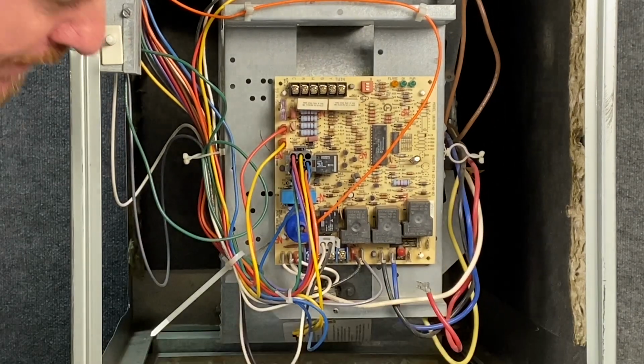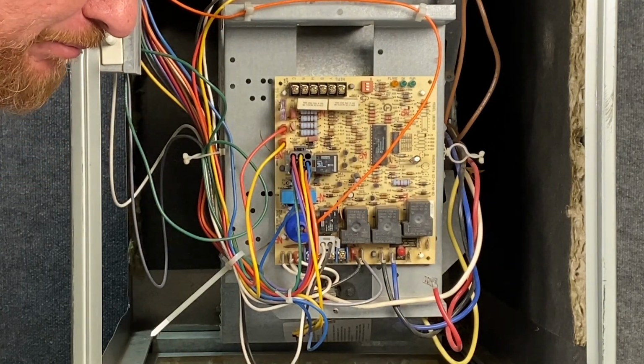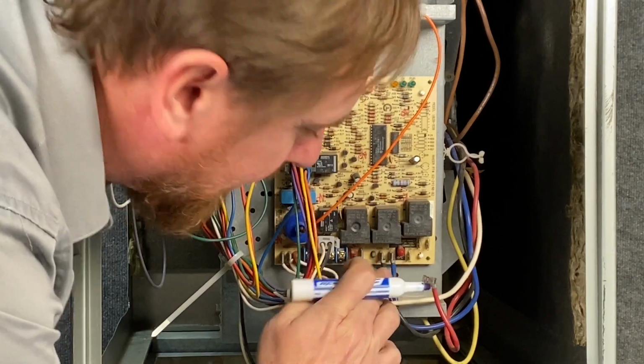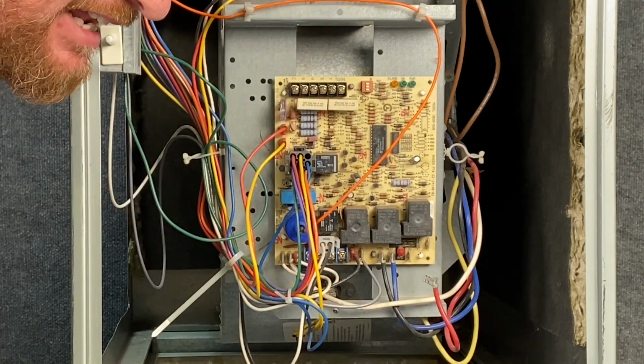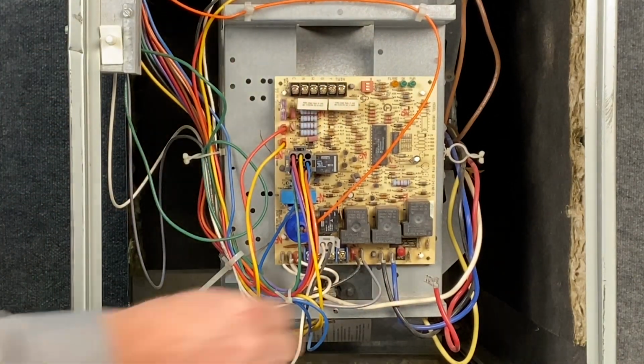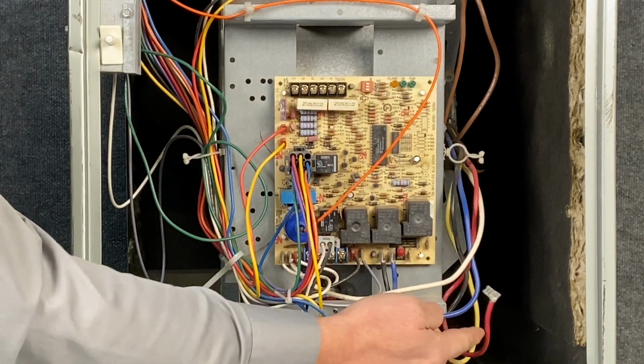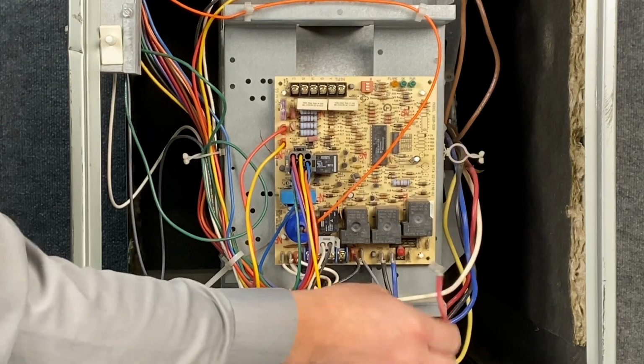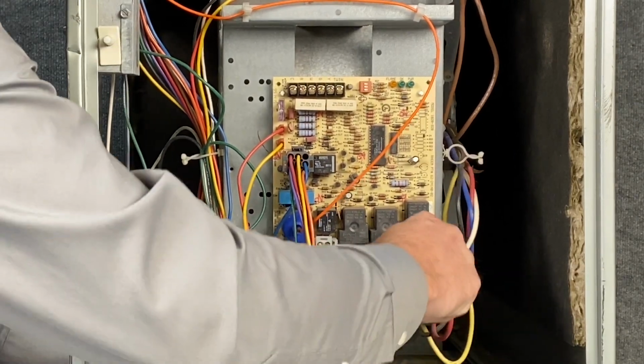And then the next wire we have is blue wire. So I'm going to write down blue, and it's on heat. So I'm going to write down heat. So what that means is this is the speed that we're going to be using for heating. So when the gas furnace fires up, it's running this speed for the heating cycle.